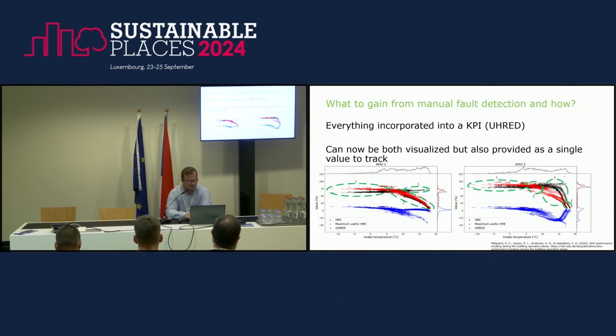If we then move to the second area, in the left plot it's in the bottom, and in the right plot it's in the middle. Here we see optimal performance. Our heat recovery efficiency is exactly where we would like it to be. If you look down at the blue UHRED, it's close to 0, which is basically what we want. But then we come to the issue that's not normally identified at all in the heat recovery efficiency. It is the cases where we're actually recovering too high amounts of heat. So we actually have an efficiency that's higher than what we would like.